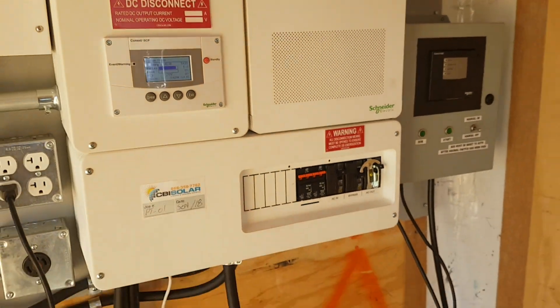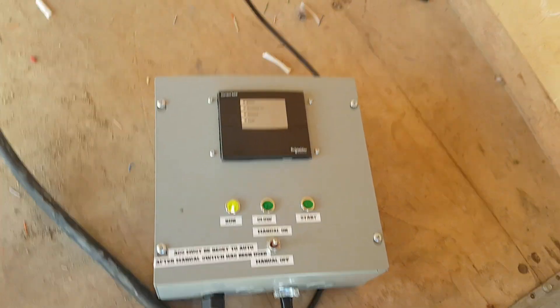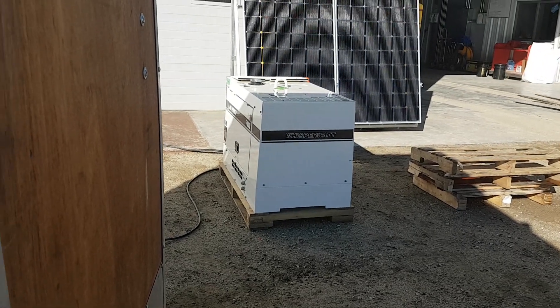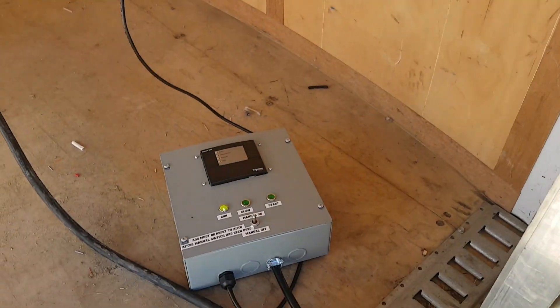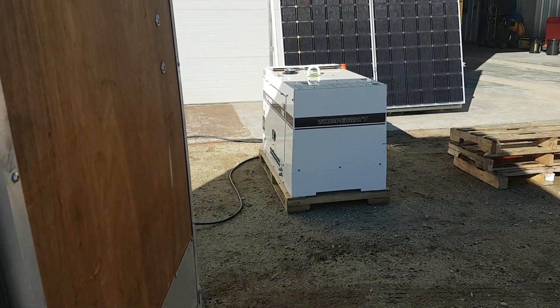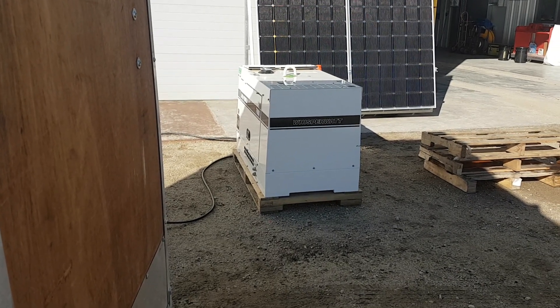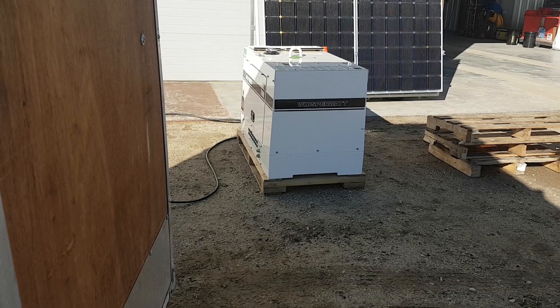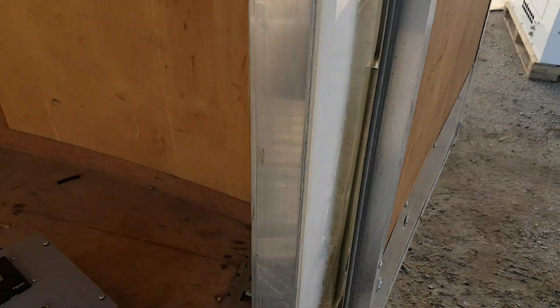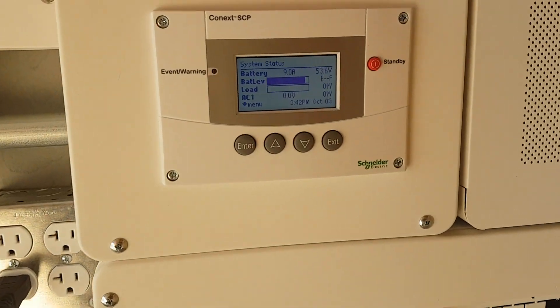We've got 54.5 — the generator is going into cool-down mode. Cool down for 30 seconds, and then the AGS will shut it off. Just waiting for 30 seconds... there we go, lights are out, it's shut down.